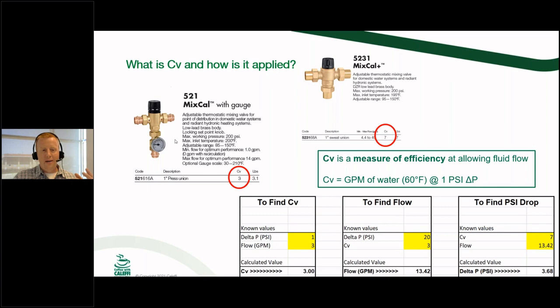Now, if you take that 521 series up to its absolute maximum, you can get 13 gallons per minute through that guy, and we max out our mixing valves at 20 psi delta P. So you take that 20 psi delta P, you plug in that 3 CV on this spreadsheet, and it's going to pop up with 13.42 gallons per minute, which is pretty common with 1-inch copper piping for your domestic hot water systems. But here's what's not common.